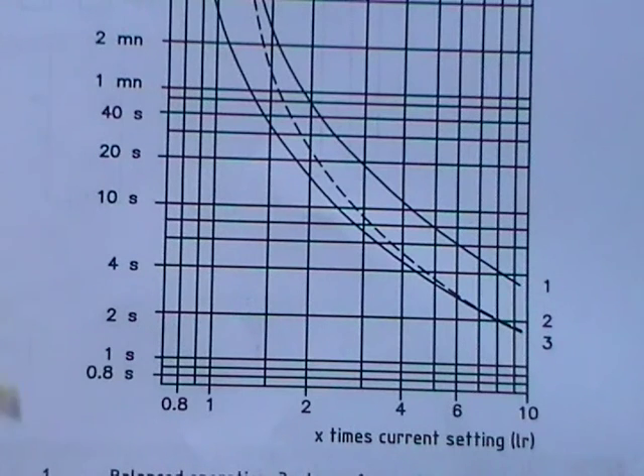So I'll let it run at that, and if I find it's tripping too early, I'll reset the trip level to something perhaps a little bit higher, and if it's not tripping out, I'll leave it where it is, or maybe even reduce it to just add a bit more protection to the generator. But there we are. That's the chart for the starter push button that I'm going to set up on the generator.